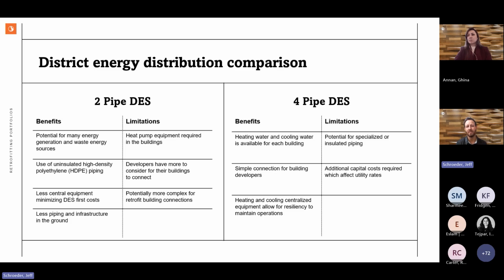At the building level within a 2-pipe system, you are looking at more equipment, such as a heat pump that would elevate the temperatures to either a heating or cooling setting as required. Whereas with 4-pipe, it's improving the temperatures in a centralized location and then sharing that energy out, so it's a much easier impact to the buildings. A new building can accept and anticipate certain temperatures within their distribution system, which can make it easier from a planning and implementation perspective.